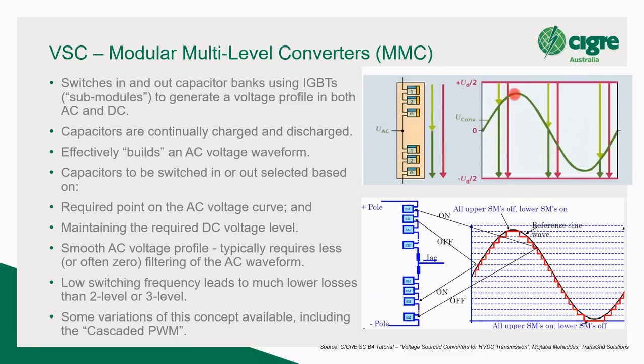So when you get to the peak of the voltage waveform up here, the same problem, it still needs to switch in 100 IGBTs because it still needs to hold that 200 kV point. But because I want to be positive, I'll have more of these switched in than those. So depending on the rating of your converter, you might have, I don't know, 80 of those switched in and 20 of those. And that process just keeps going as you go through the AC voltage waveform and throughout its operation. So this is the beauty of the MMC.